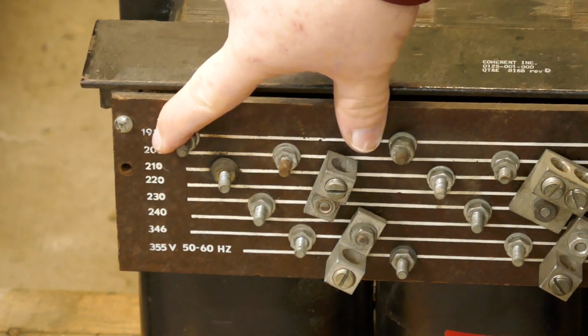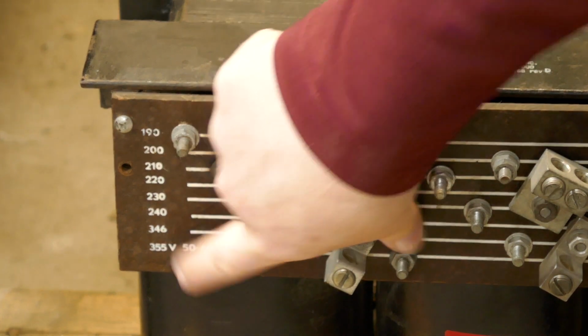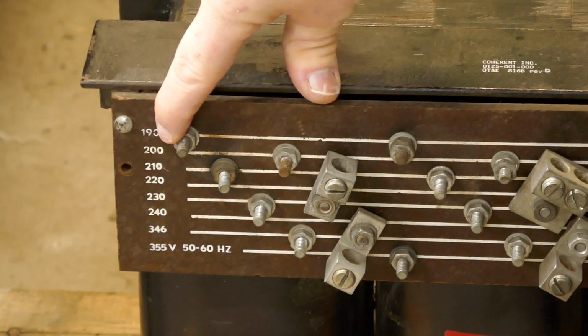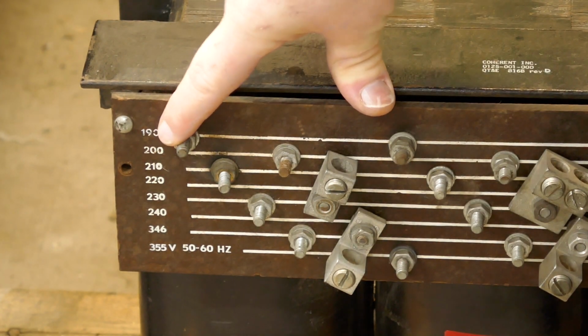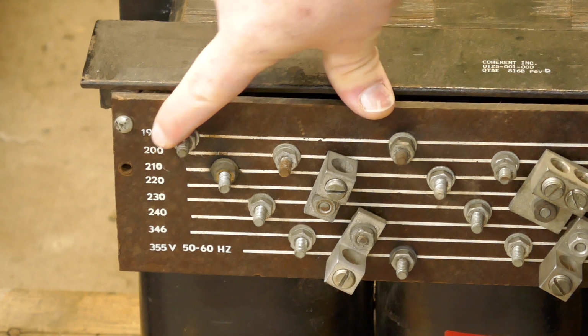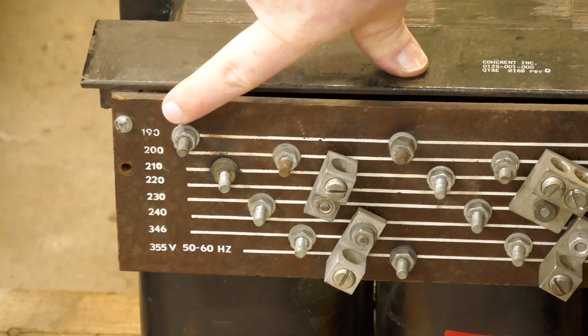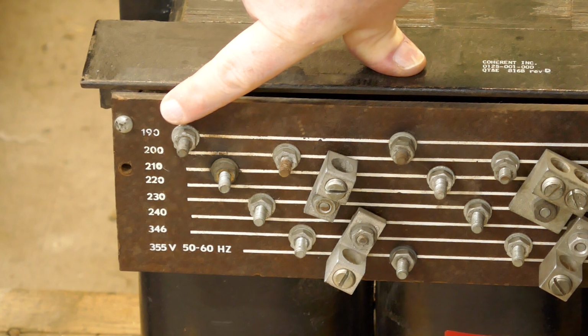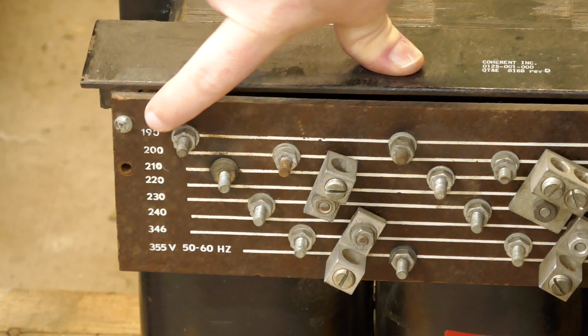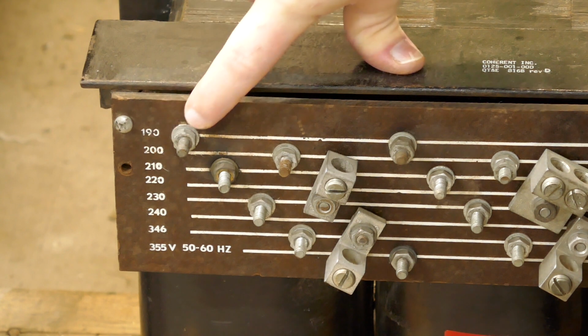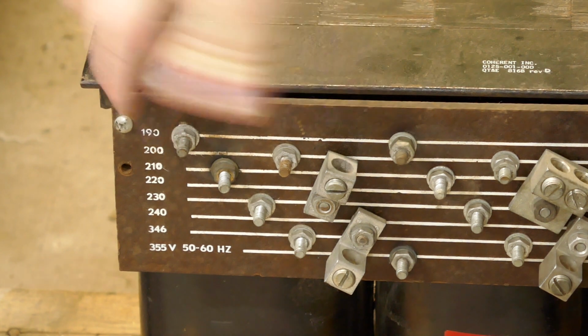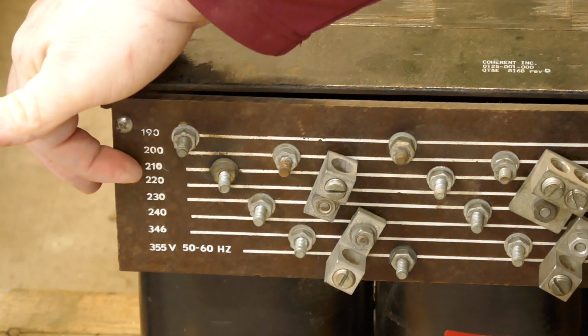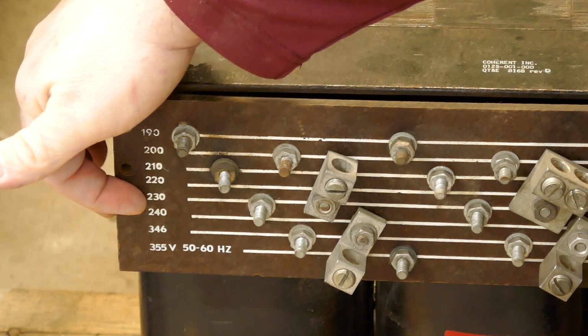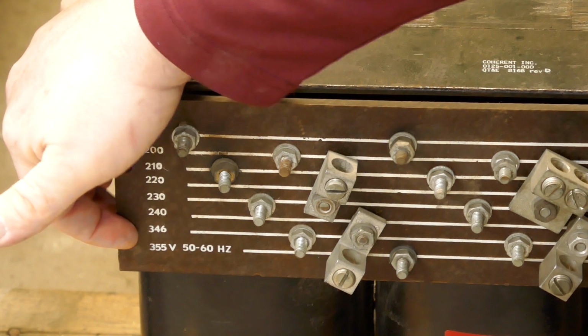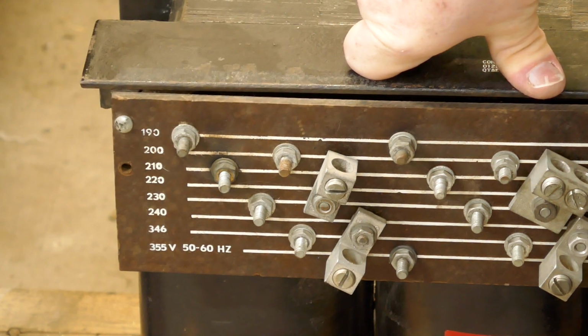So it has everything from 190 to 355 volts. Let's say I had a 220 service, nominal 240 in my house, and I've got a phase converter. Let's just say, for instance, that my voltage was really low for some reason. This 190 tap right here, I can make that the input, and then I can get 200, 210, 220, 230, 240, 346, or 355 out.